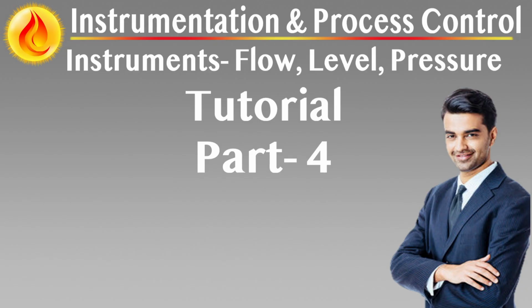Signal and output integration. Pulse output is standard, ideal for connection to totalizers, PLCs, or flow computers. Mechanical or magnetically coupled counters can be used in hazardous or isolated areas. Where multiple outputs are required, e.g. batching and recording, use dual pickup systems with independent signal conditioning.